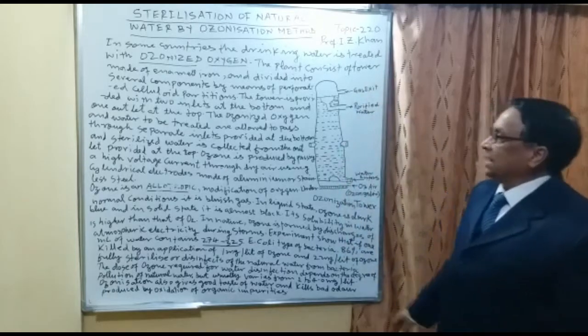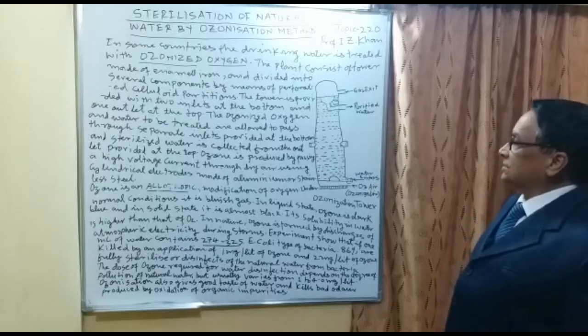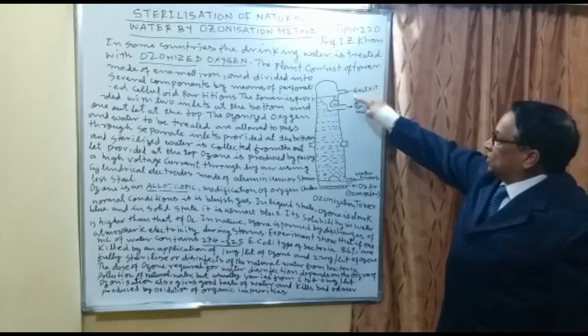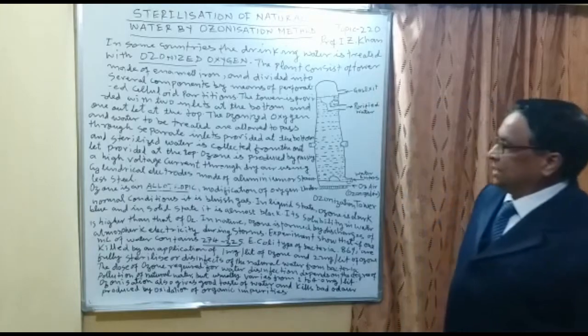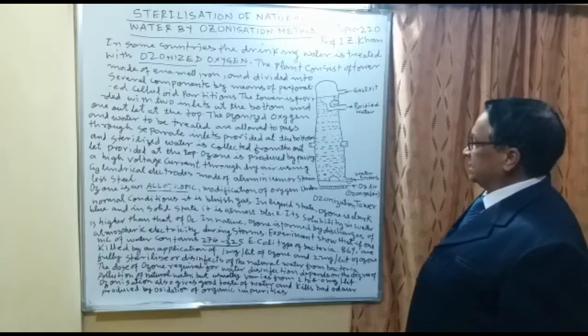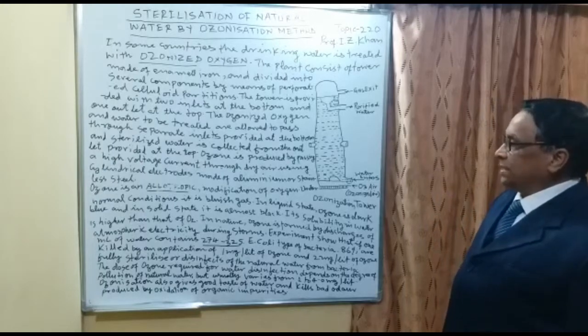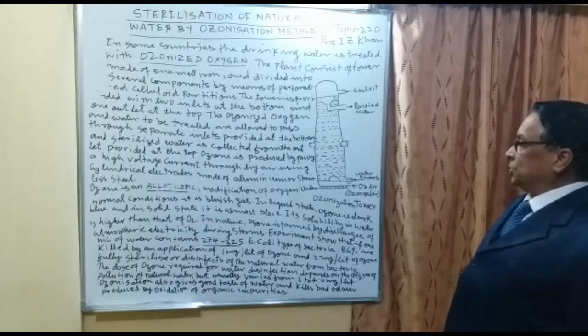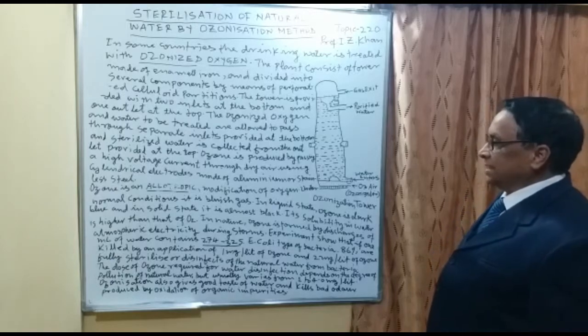The tower is provided with two inlets at the bottom and one outlet at the top. This is the outlet from where the treated ozonized water is collected. The ozonized oxygen and water to be treated are allowed to pass through separate inlets provided at the bottom, and sterilized water is collected from the outlet at the top.